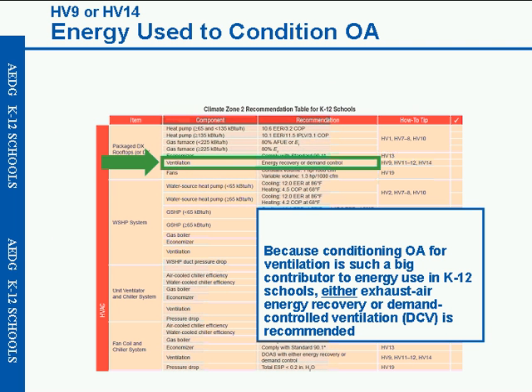Here's an example for a package DX rooftop system type. There are ventilation recommendations for every single system type, and in this case, you'll see that the recommendation for ventilation control is either demand control, which would be a CO2 sensor, or energy recovery. The idea is that reducing ventilation outdoor air loads can be done through either mechanism, demand control ventilation or energy recovery ventilators. Some system types lend themselves better to demand control ventilation, and other system types, such as the bigger central outdoor air systems like the VAV systems, lend themselves better to energy recovery. And so we provided some flexibility in handling ventilation efficiently.